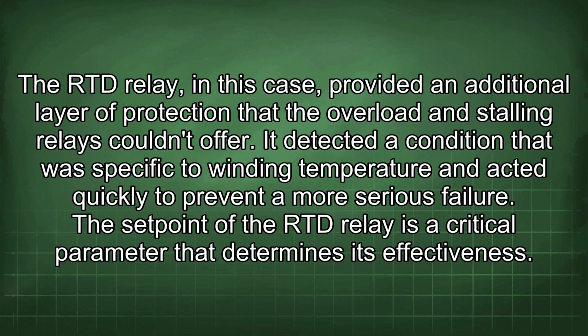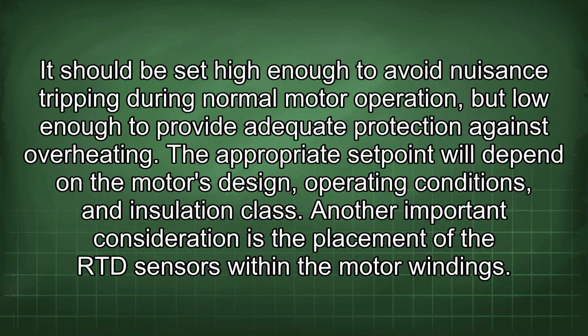The RTD relay, in this case, provided an additional layer of protection that the overload and stalling relays couldn't offer. It detected a condition that was specific to winding temperature and acted quickly to prevent a more serious failure. The set point of the RTD relay is a critical parameter that determines its effectiveness. It should be set high enough to avoid nuisance tripping during normal motor operation, but low enough to provide adequate protection against overheating. The appropriate set point will depend on the motor's design, operating conditions, and insulation class.